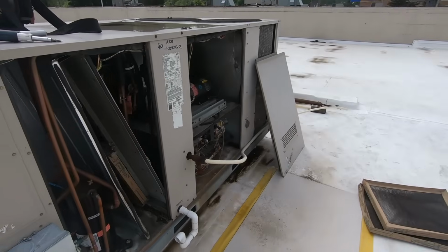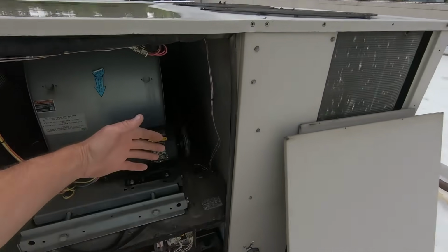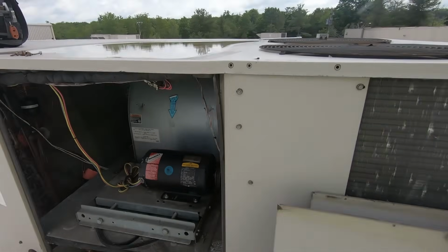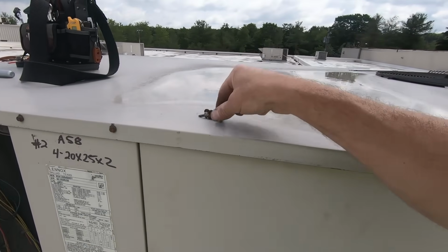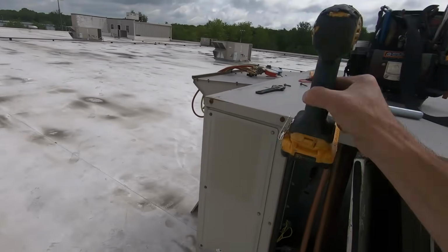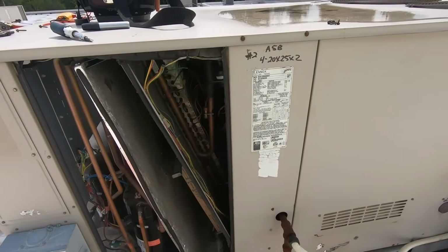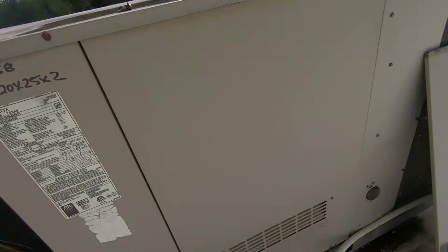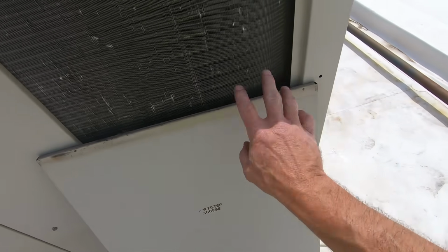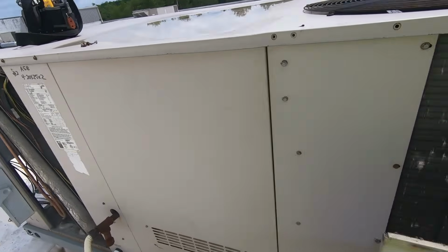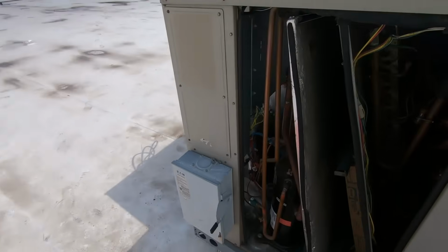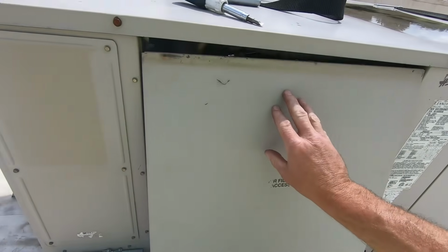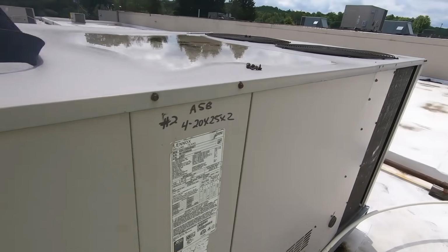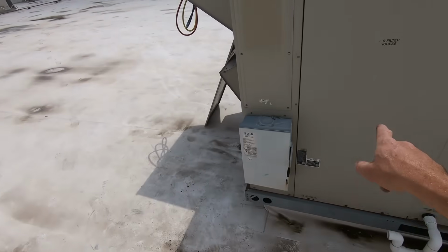Well, I figured I'd start with the blower. And it's going to get a belt. And that pulley's wound all the way in and the motor's clicking. So, as long as it's running right now, that's all I care about, because it's going to get replaced. We get the screws in this, get this panel on, we're going to kick on some AC. All right, guys, and as you can see, this panel's not leaning up against the coil. Just for everybody out there who's concerned. Not touching the coil, simply touching the cabinet. Blower door's in place, that still needs screws.